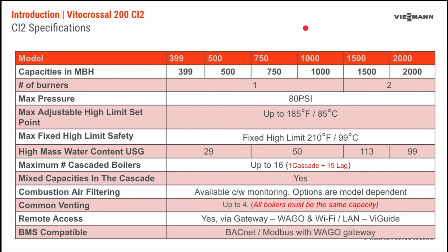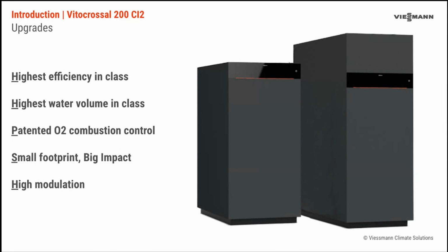or Modbus with communication via the Wago gateway. So some quick takeaways here: highest thermal efficiency in class, highest water volume in class. So key thing to remember here: high water volume, high mass boiler. The Lambda Pro 2, this is a patented O2 combustion control. So we are utilizing a very robust oxygen sensor in the combustion zone. And small footprint, big impact.